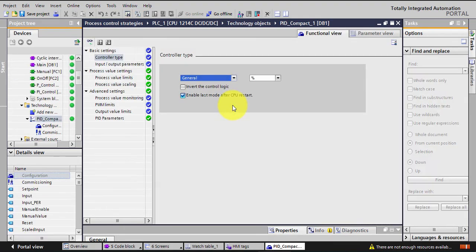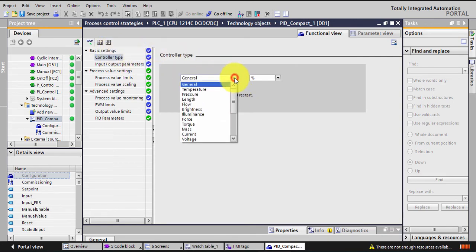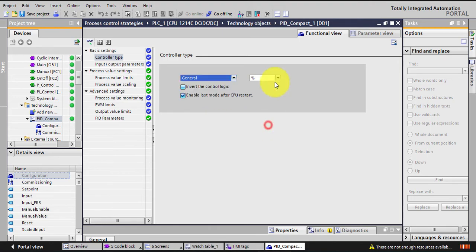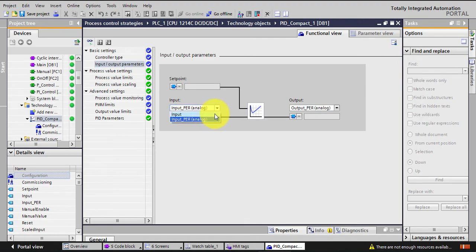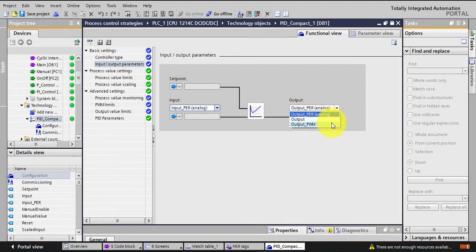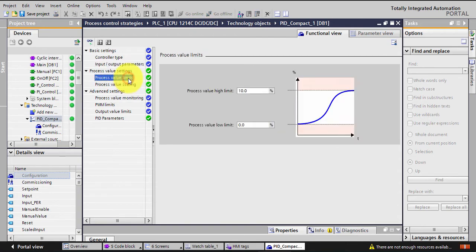In the configuration window, under basic settings, you can choose the controller type — temperature, pressure, length — and the unit. From the parameters section, you choose whether to use input percentage or raw input, and whether to use output percentage or pulse width modulation output.